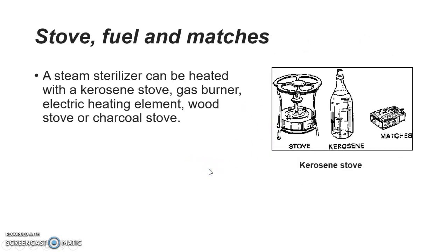Next is stove, fuel and matches. A steam sterilizer can be heated with a kerosene stove or a gas burner or electric heating element or wood stove or charcoal stove. So commonly, what we use most is either gas burner or electric heating element.